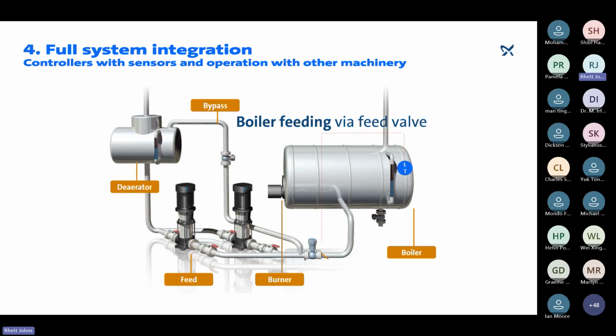And then you've also got the pressure loss across the feed valve leading to a larger feed pump. And then you've got your slow reaction time. These modulating valves open slowly and they close slowly. So you can end up with a system that has thermal shock when the colder water is introduced in large quantities and it's not regulated in a tightly controlled manner. And then you've also got poor economizer heat pickup of the energy.